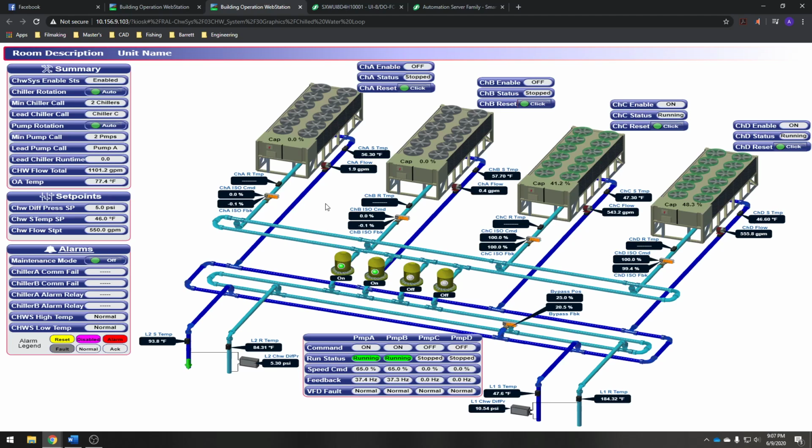And we didn't have isolation valves, so even when chillers were off, you were still flowing water through them. So water was flowing through these, adding head pressure. We were losing pressure through the pipes and things of that nature. So that's why we added these motorized isolation valves, so we can actually turn these off so water is no longer flowing through these systems.